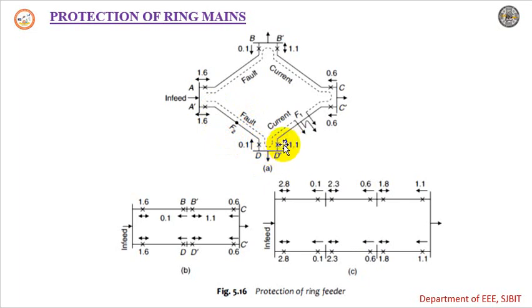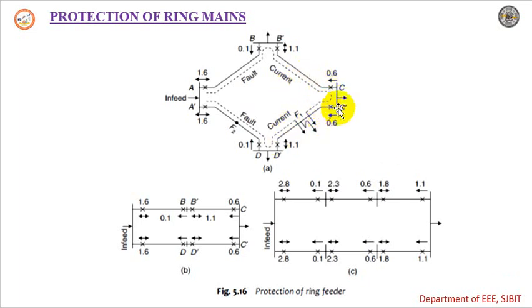The non-directional relay present here will trip. The directional relay at C', since the current is flowing in the same direction as the arrow, will trip. The non-directional relay at D' will also trip. Thereby, the faulty feeder will be disconnected from the ring mains.